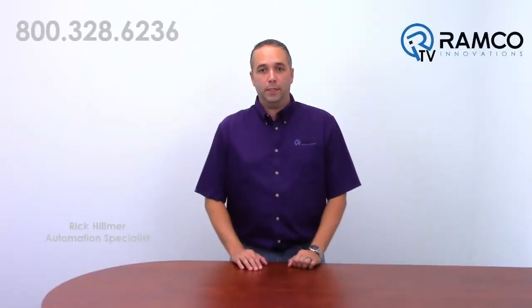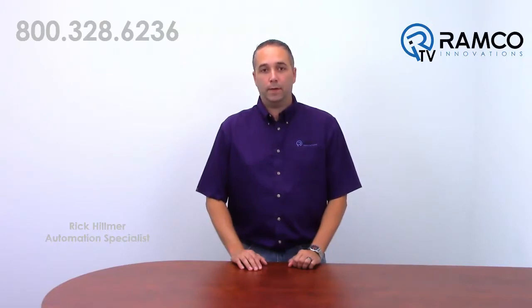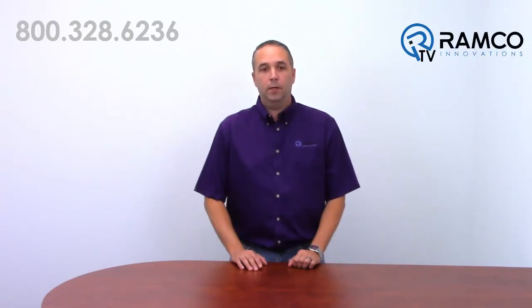Hello and welcome to Ramco TV. Today we'll be taking a look at a recent build we completed in our UL 508A panel shop. The system consists of three ACS 880 wall mount drives wired up in a common DC bus configuration. This common DC bus allows regenerative power from braking motors to be used by the driven motor. This eliminates the need for braking resistors or active front end drives. Let's take a look.